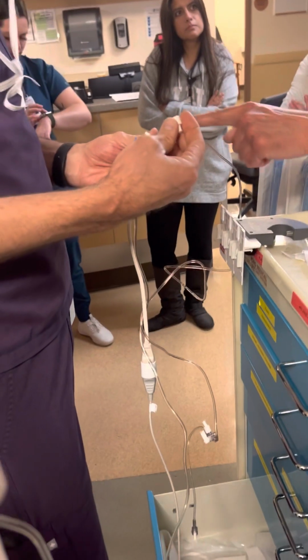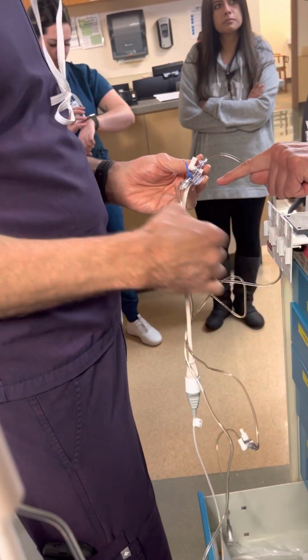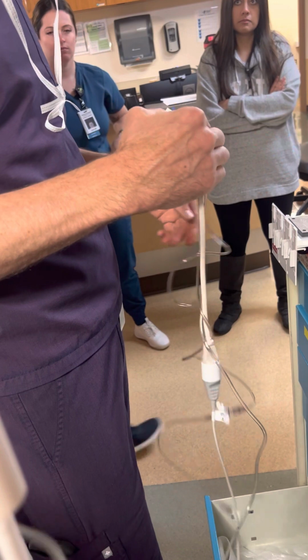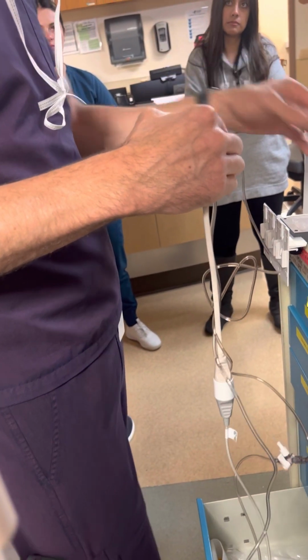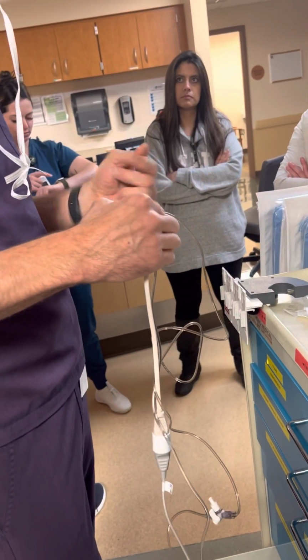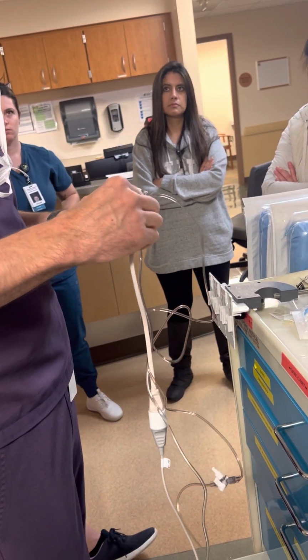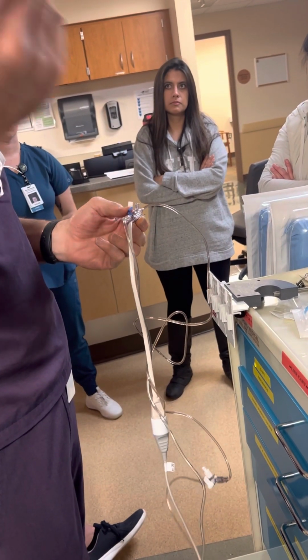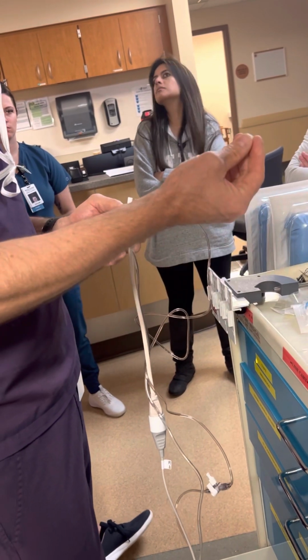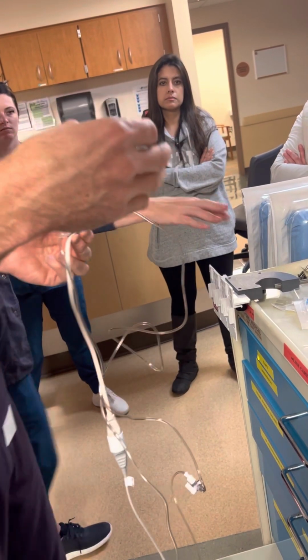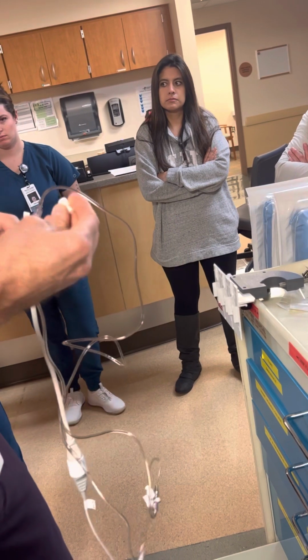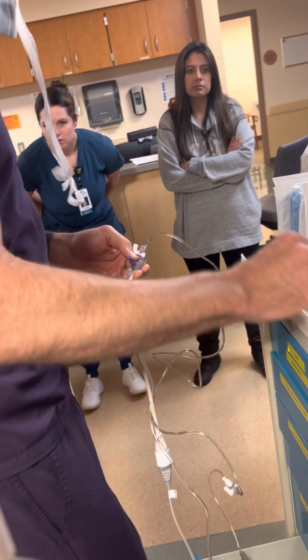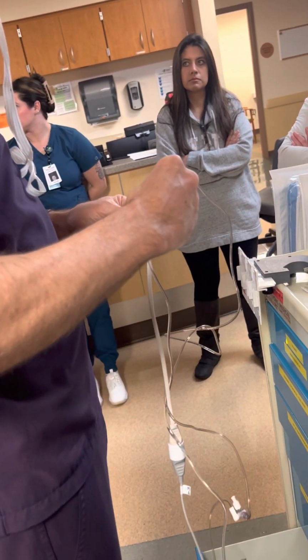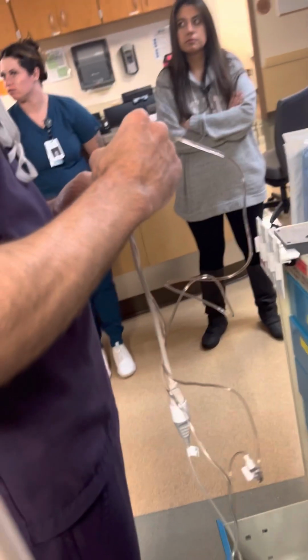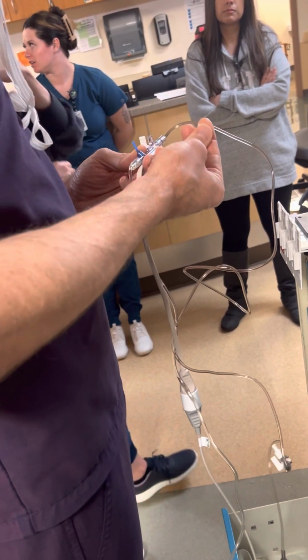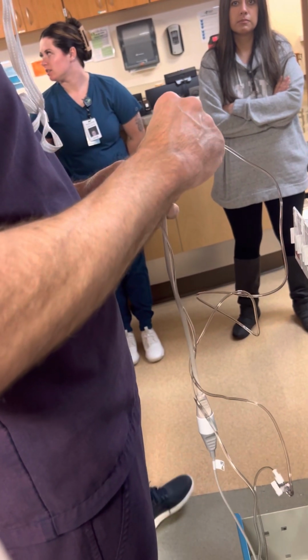I mean, that's the thing. This port allows the air pressure to reach the transducer. When I'm doing this, the old caps are on there, and they open to air, and then I replace those caps once I've zeroed it. Yeah, and they have little caps that they replace them with. So I guess there are those in the demonstration. When I started, I put these on, so then I replace them with those. With this cap on there, it still opens to air.